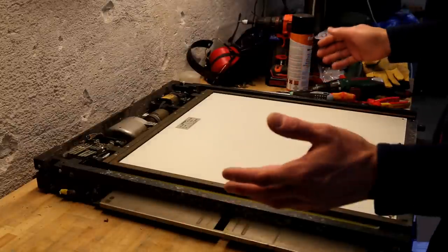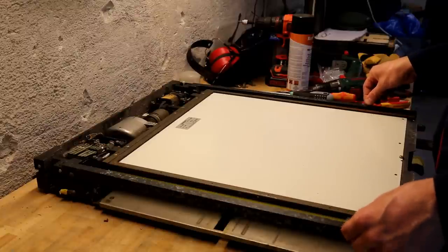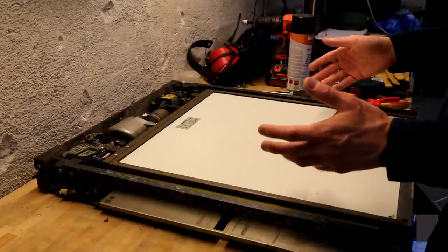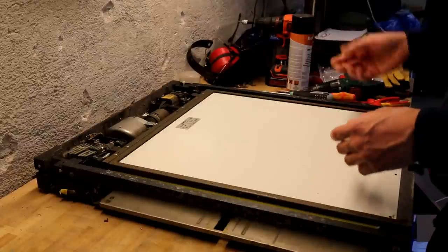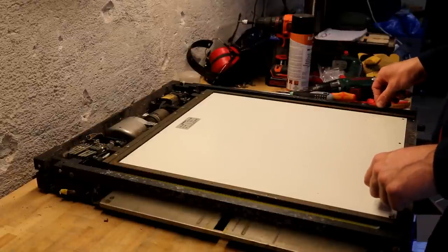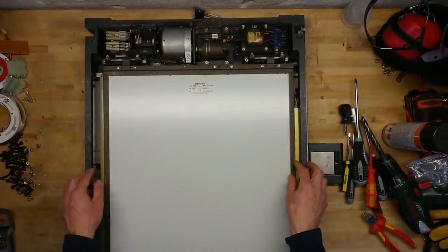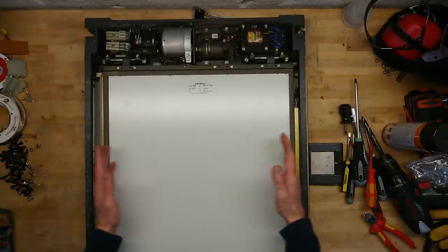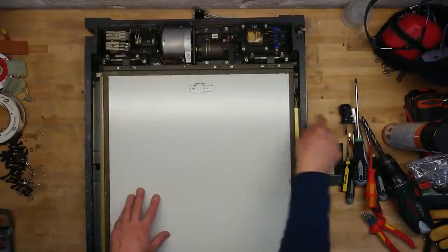Now this huge item is the image plate, and it's a little different from what I expected. Because I expected just to see a phosphor plate, maybe some kind of automatic X-ray detection, and then you can just put in your cassettes with the film in. But this actually has a motor with a curved surface on it here, so it can move this plate back and forth in this direction. Now, from what I can gather, this is called a grid plate. It has 12 rows times 40. So it's simply slits in a lot of rows and columns. Also has Pb.